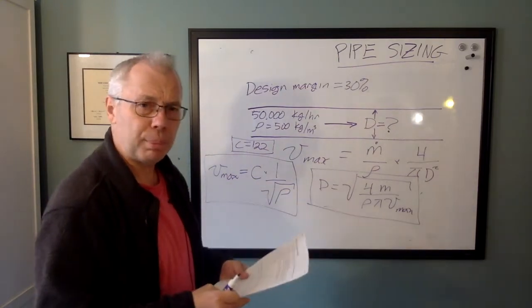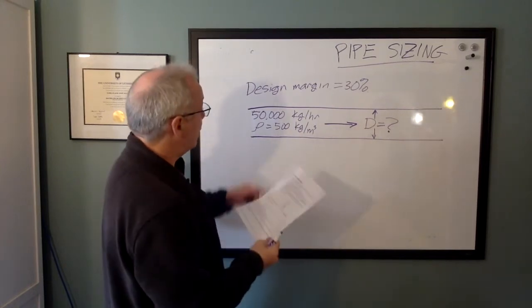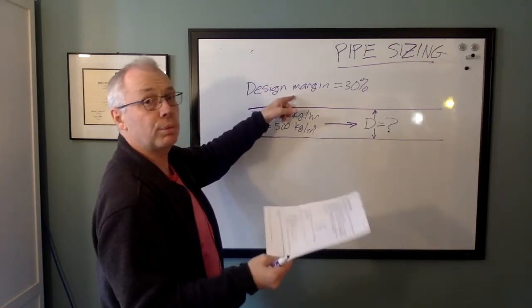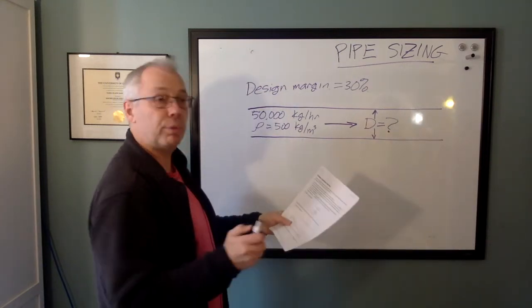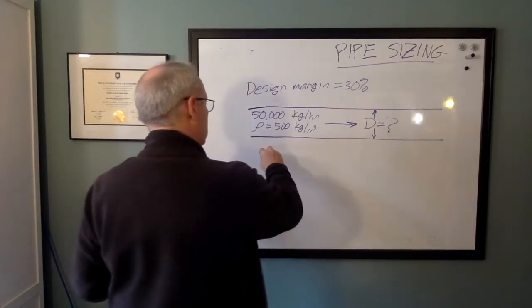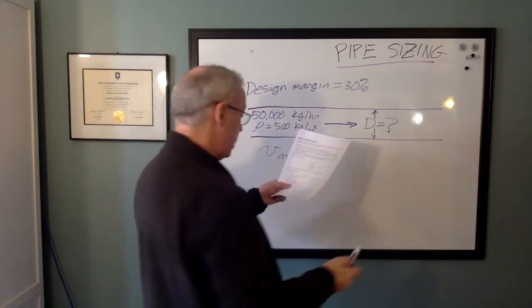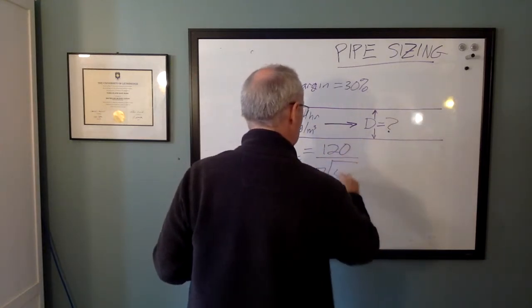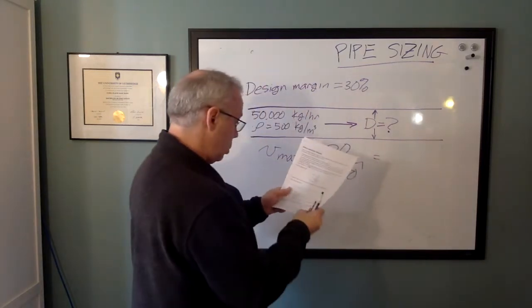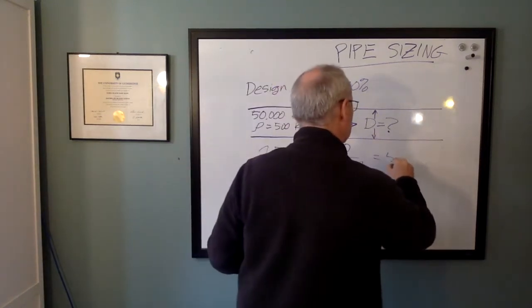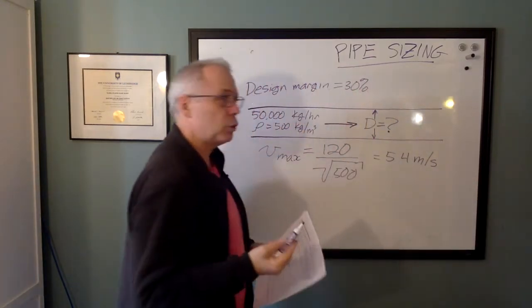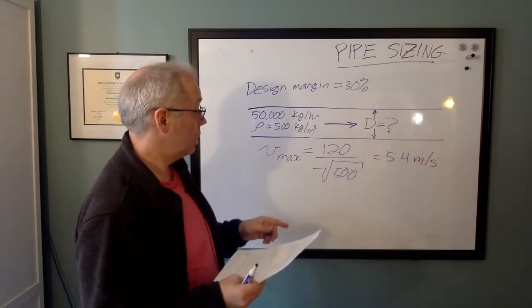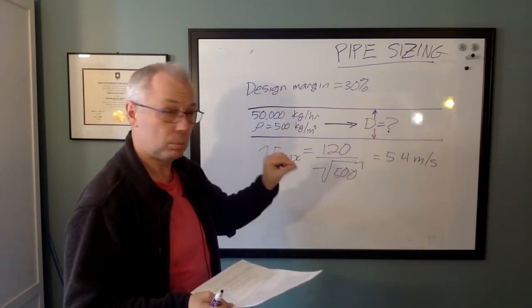So let's work through an example. For our example, we have 50,000 kilograms per hour, density of 500 kilograms per cube, and a design margin on flow rate of 30%. And first, we will find the maximum velocity. So Vmax, and we'll use this magic C factor. We'll call it 120. That's the number I typically use. 120 divided by the square root of 500. And that number is equal to 5.4 meters per second. So this says we should not allow the fluid to go faster than 5.4 meters per second. So we will pick that as our design velocity. That's our criteria. 5.4 meters per second.